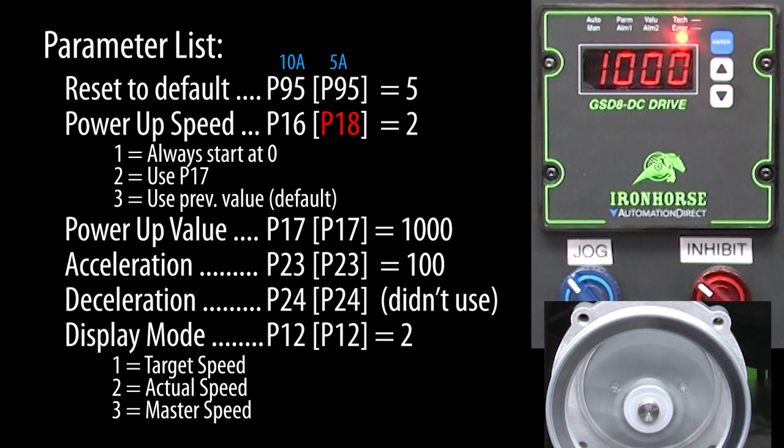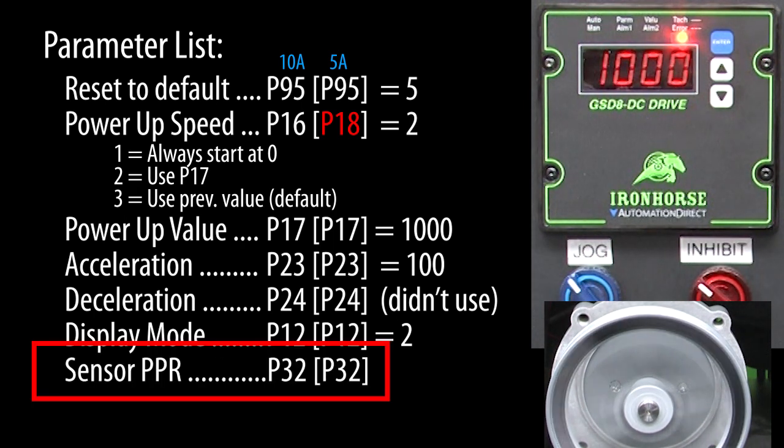What if instead of an encoder you have some other pickup sensor generating the feedback pulses coming back into the drive? Maybe you have a flow meter that sends out pulses representing gallons per minute or a gear tooth sensor counting the number of teeth passing by. You can use any sensor you want as long as it is generating a digital waveform between 0 and 5 to 24 volts DC. Just enter that sensor's PPR in parameter 32.